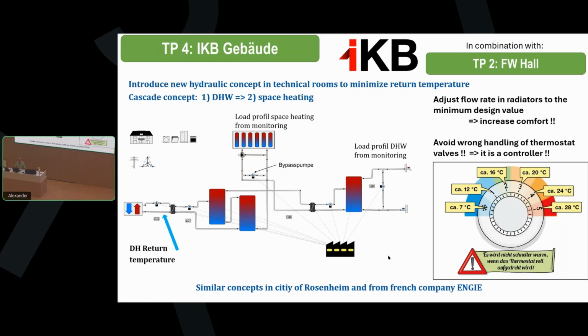At the next point, unfortunately, I would say 70 to 80% of the population does not know how a thermostat valve really works. It's very often used just as an on-off valve, and the numbers, as we see here, 1, 2, 3, 4, 5, most people think this is power. If I have 5, then it's a lot of heating power. If it's 1, I have less. In real life, this is temperature. So if I have 3, I have 20 degrees.